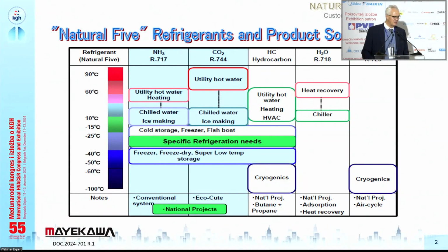And the second refrigerant is CO2. The CO2 application started, in fact, with screw compressors entering the market in '64. And from there we started with CO2 liquefaction plants, but the technology with CO2 is 60 years already available and to be promoted continuously. The third column is the hydrocarbons, which was introduced at the same time the screw started on the market, mostly at petrochemical plants in the beginning. So these first three columns are using oil lubricated compressors, piston and screw. The fourth column, water, does not need a compressor.